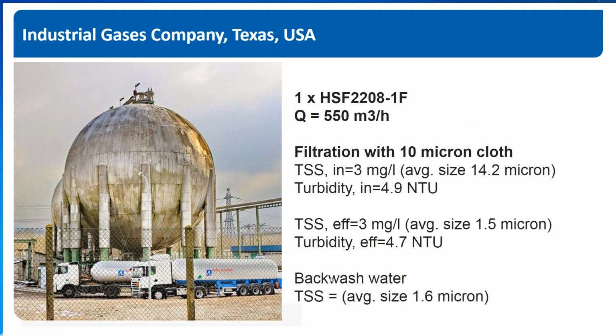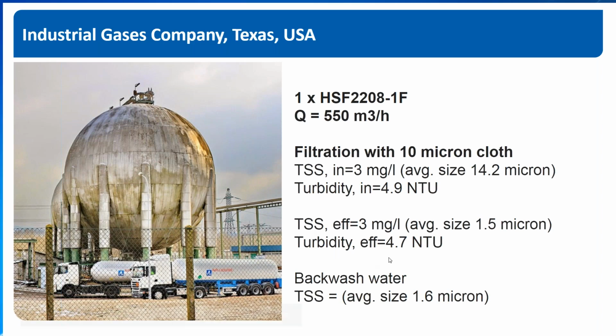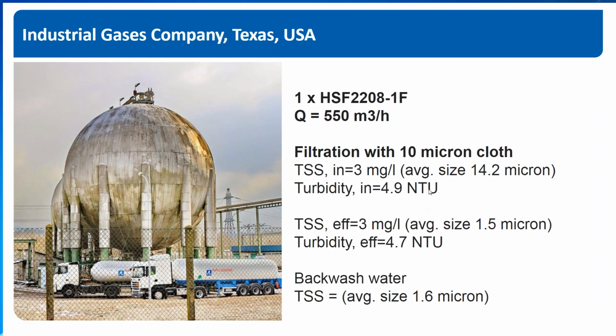We do see that we get some solids in the backwash, and the customer says that they are very satisfied with the unit. It keeps the water extremely clean, and they have been able to skip a planned shutdown, which they had planned to do to clean out the basin. So they've been able to reduce the frequency of shutdowns at the cooling tower.